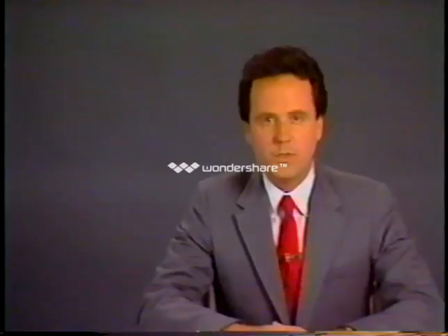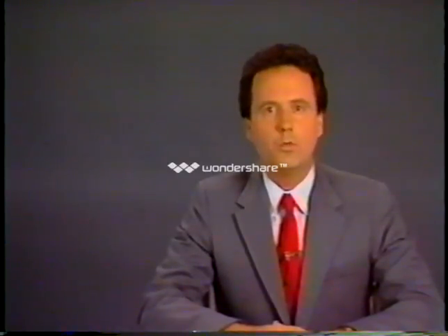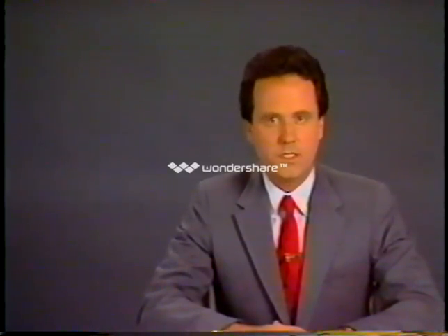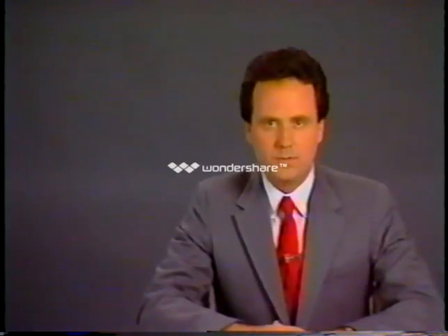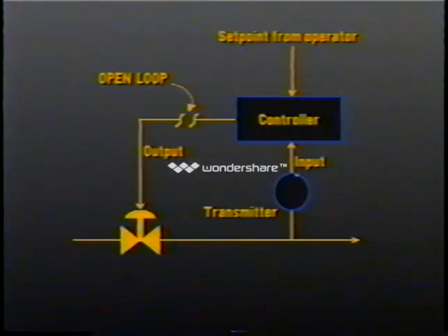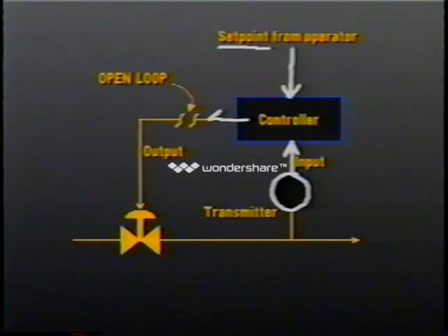If any part of the loop is broken, automatic control will not be possible. This condition is called an open loop. As you can see, the sensor and transmitter still provide the process input to the controller, and the operator continues to provide a set point input. The PID controller is still performing its function according to the settings on its 3 modes. However, we can't get our control signal to the valve because our loop is open.